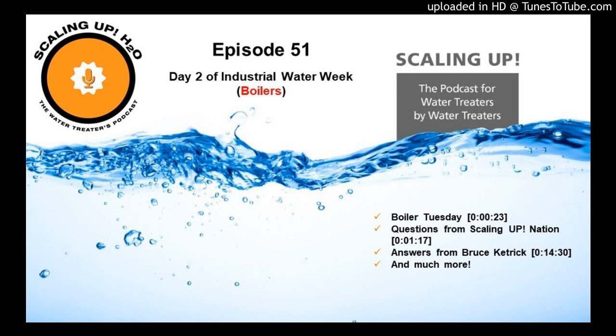In the below 30 psi boilers, what you're looking at is usually heating boilers, high condensate return, things along those lines. In those applications, that's where our one-drum treatments come into play, where we're looking at more oxygen scavenging, running a sulfite at a level anywhere from 30 to 60 parts per million, as high as 80 parts per million, and then a good dispersant because you've got a very high condensate return.